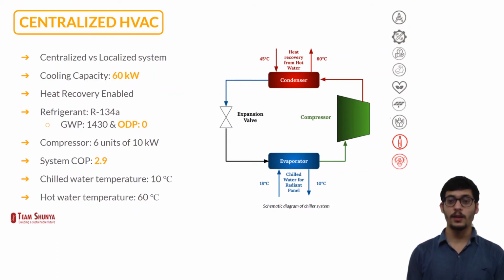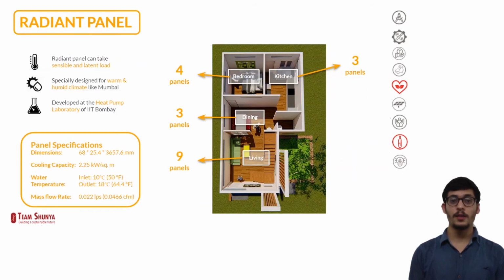The refrigerant used is R134A, which has zero ozone depletion potential, and the COP of the whole system is coming out to be 2.9. Radiant panels are placed in individual rooms for providing cooling. These radiant panels can take both latent and sensible loads, which are specifically designed for warm and humid climate like Mumbai. These panels are developed at heat pump laboratory of IIT Bombay. The panel specifications and number of panels needed in each room are shown in the graphic.